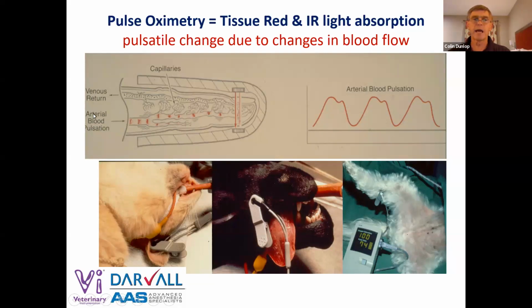So if we took a knife and cut my finger longitudinally here and threw that bit in the bin, I'd have half as much tissue, half as much background light absorption. This line would come down half that amount, dragging this waveform down by that amount, which is going to pull the saturation reading down. So the saturation fell because of a change in background light absorption, not oxygenation. And the change in the background light absorption that happens in anesthesia is vasoconstriction, most commonly due to painful stimulation, but it could be due to hypothermia, perhaps drugs, some of the drugs we give causing vasoconstriction, reducing blood flow, and that alters the oxygen value.